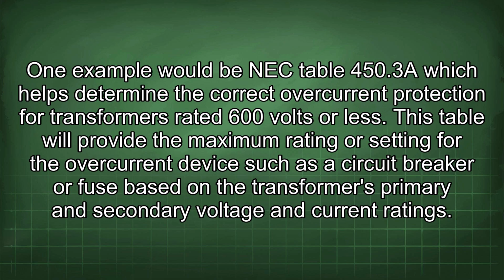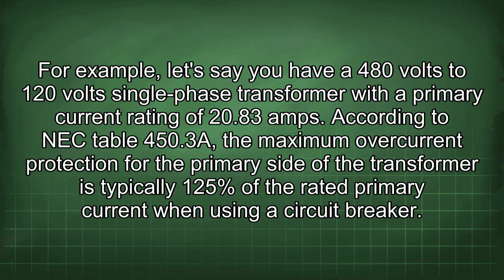One example would be NEC Table 450.3, which helps determine the correct overcurrent protection for transformers rated 600 volts or less. This table will provide the maximum rating or setting for the overcurrent device, such as a circuit breaker or fuse, based on the transformer's primary and secondary voltage and current ratings. For example, let's say you have a 480 volts to 120 volt single-phase transformer with a primary current rating of 20.83 amps.